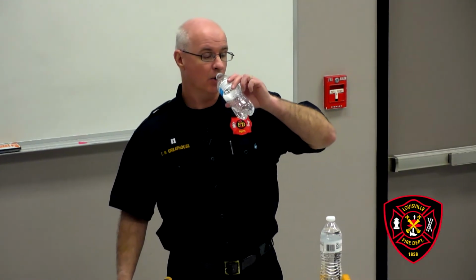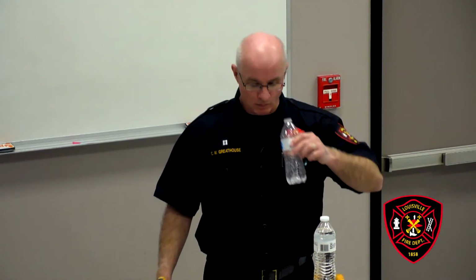The most common problem is an air leak on the intake side of the pump. Another place air can enter the pump is a whirlpool at the strainer, or you can have air leakage due to defective pump packing, or other areas I've already talked about.